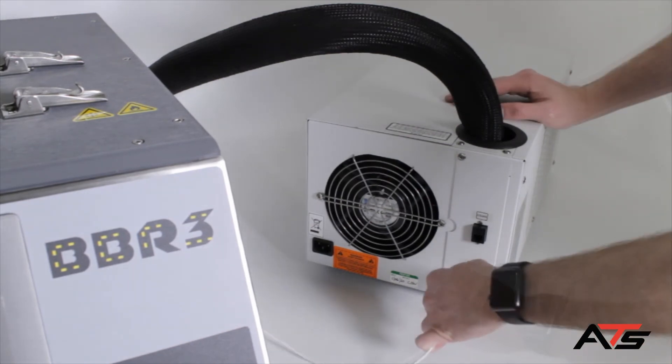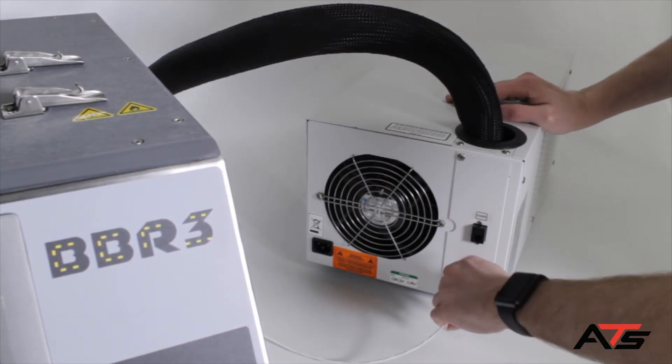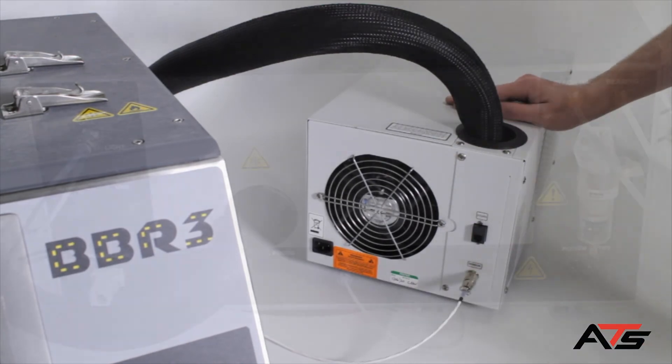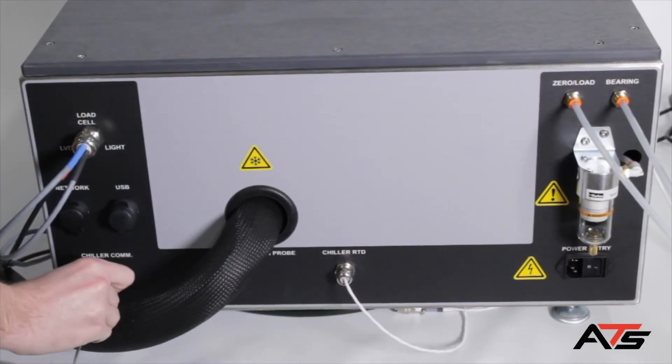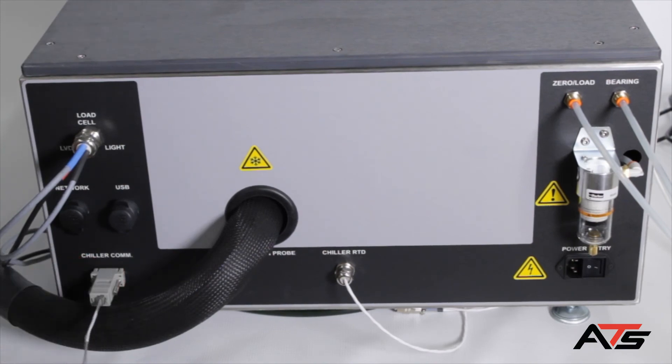Connect the chiller RTD cable from the rear of the base unit to the refrigeration unit. Connect the chiller communication cable between the chiller communication port on the rear of the BBR and the RS-485 port on the rear of the chiller.